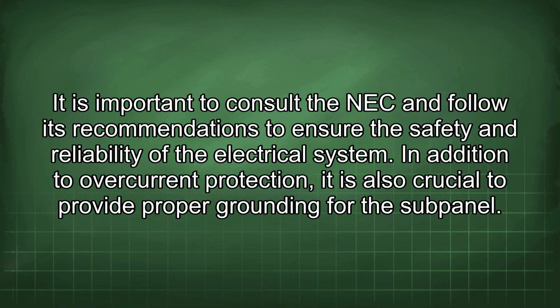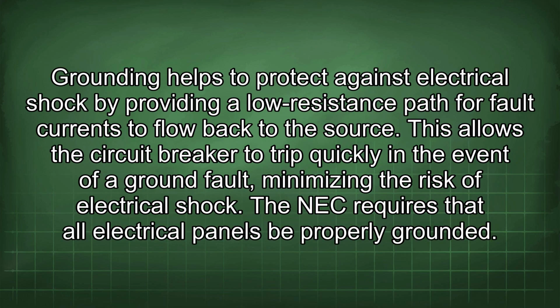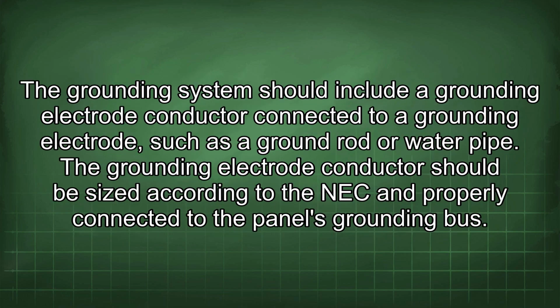In addition to overcurrent protection, it is also crucial to provide proper grounding for the subpanel. Grounding helps to protect against electrical shock by providing a low resistance path for fault currents to flow back to the source. This allows the circuit breaker to trip quickly in the event of a ground fault, minimizing the risk of electrical shock. The NEC requires that all electrical panels be properly grounded. The grounding system should include a grounding electrode conductor connected to a grounding electrode, such as a ground rod or water pipe. The grounding electrode conductor should be sized according to the NEC and properly connected to the panel's grounding bus.